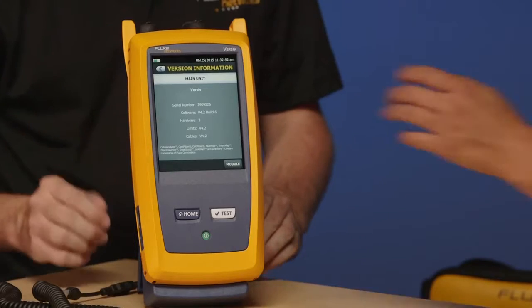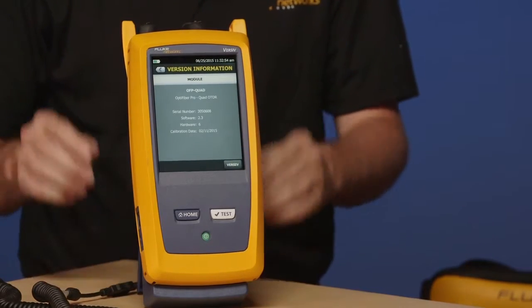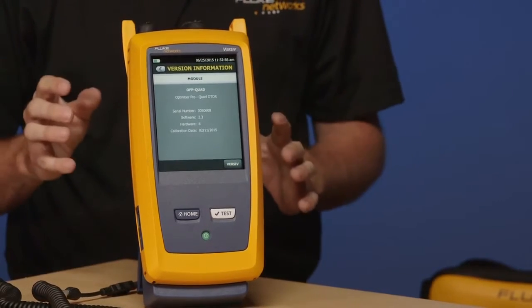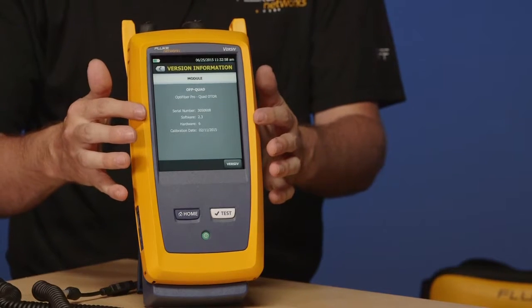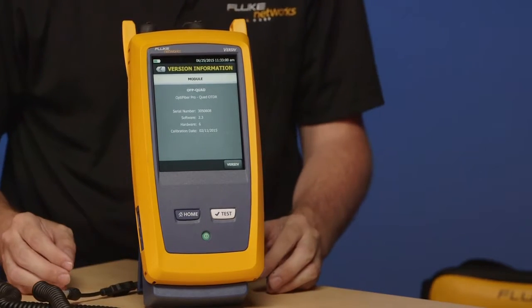Whenever you download test results to Linkware PC, if it's connected to the internet, it will actually check for you to see if you've got the latest software version. Go ahead and tap Module for me. Now we're interrogating the module that goes in the back there, and you can actually see the calibration date on there. How often should I calibrate?